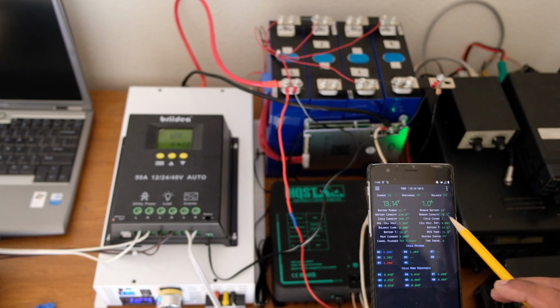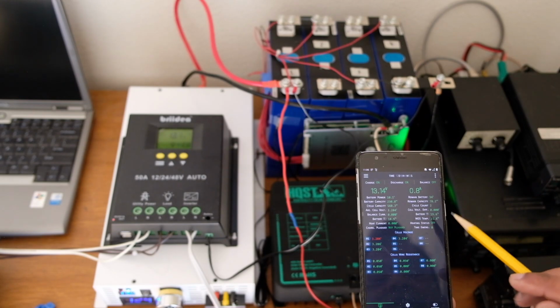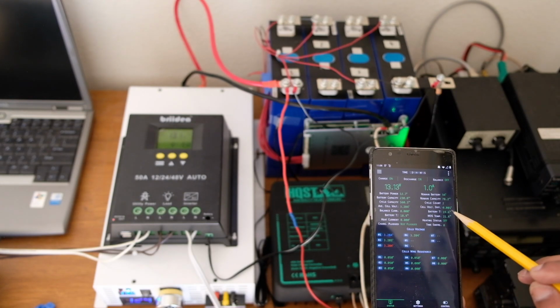The remaining battery capacity is 34%. Remaining capacity in ampere hours is 78. Number of cycles it has gone through is 2 so far. Cell voltage difference - these are the individual cell voltages, all of which are 3.284 right now. Once they exceed 5 millivolts, the balance current will turn on.